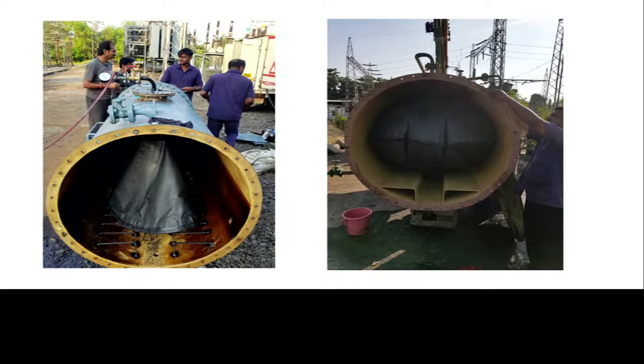2/3 portion of the conservator should be open, meaning there should not be oil. Otherwise what will happen, the air cell needs the 2/3 portion for expansion. Otherwise there will not be any breathing, and it will increase the pressure in the transformer, causing PRV tripping or oil leakages to start. So minimum oil is required.